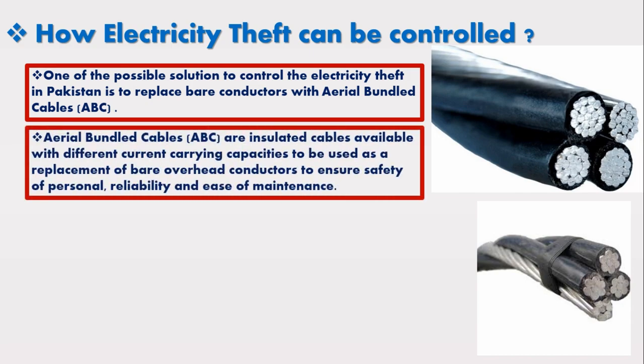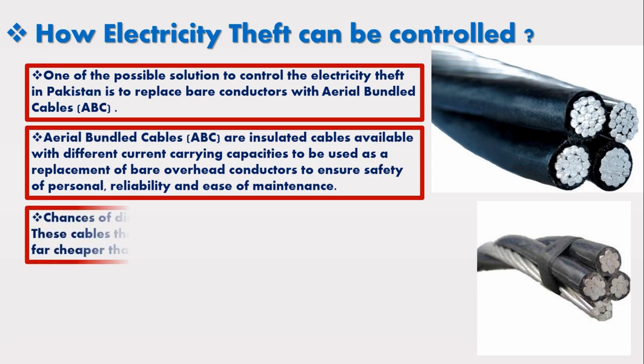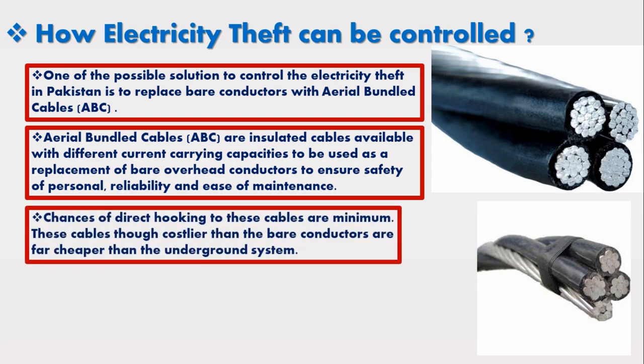Aerial bundled cables are insulated cables available with different current carrying capacities, to be used as a replacement of bare overhead conductors to ensure safety of personnel, reliability, and ease of maintenance. Chances of direct hooking or kunda to these cables are very minimum. These cables, though costlier than the bare conductors, are far cheaper than the underground system.